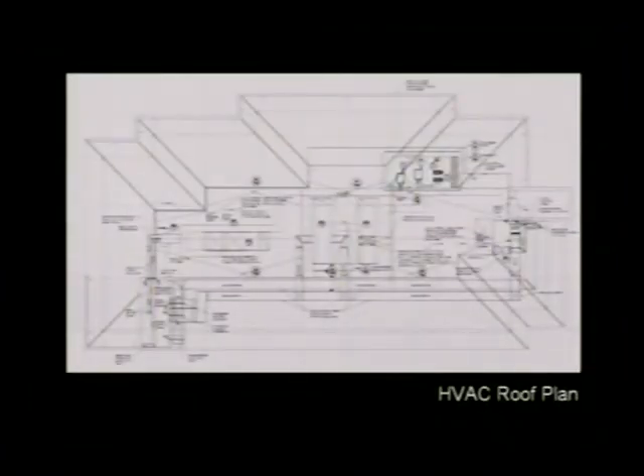You can see in the center there the two low pressure VAV rooftop units that are supplying the floor, and those big ducts run out through the mansard roof and go down. Those air handlers were sized using that model, not exactly how we size them, but to figure out the reduced amount of air and tonnage that we needed. And then we also put in pressure dampers in the system so that in the morning on the east side, as the sun comes up and rolls around the building, the east and the south side is where the majority of the cooling load is. With those pressure dampers, we can actually shift that air from the east to the west side as the load changes throughout the day. So that's why we have the large ducts that are the same size on both sides being fed off the same units.